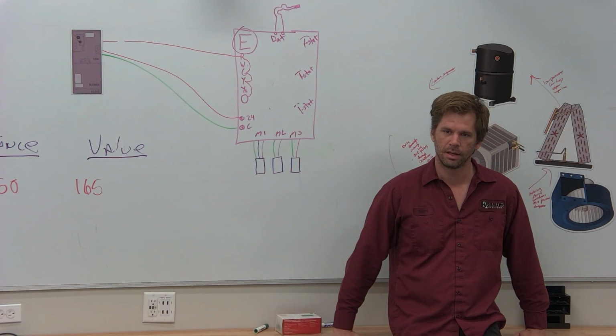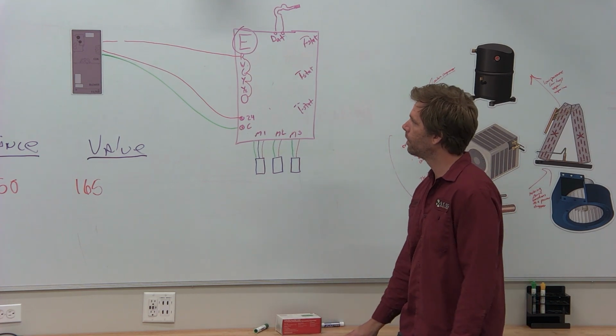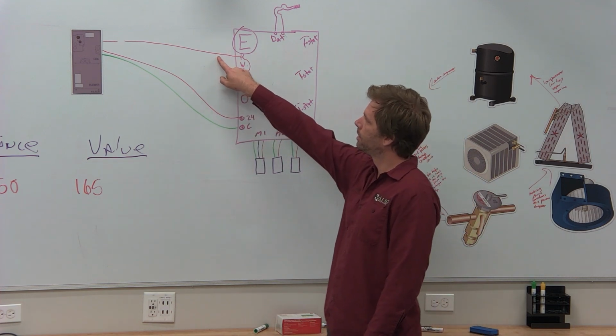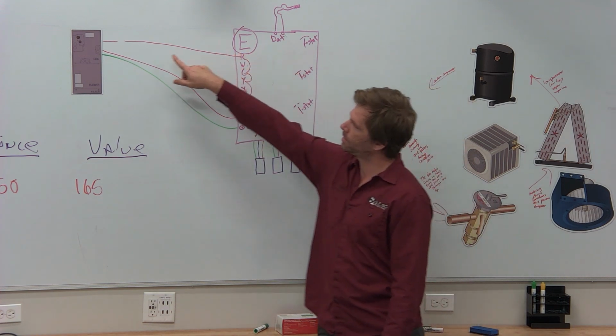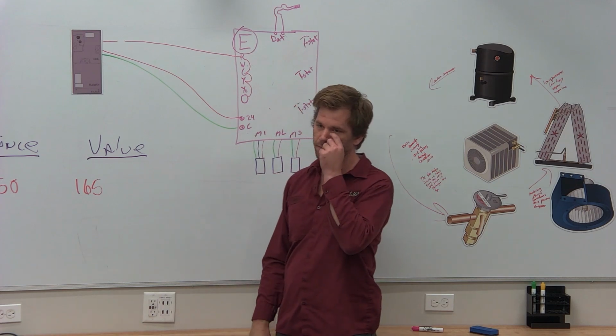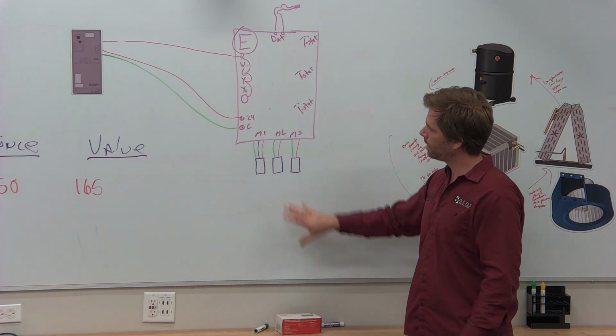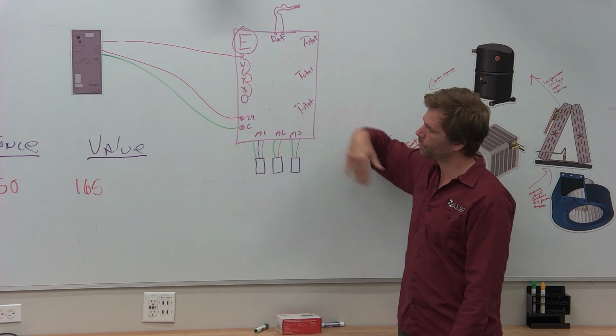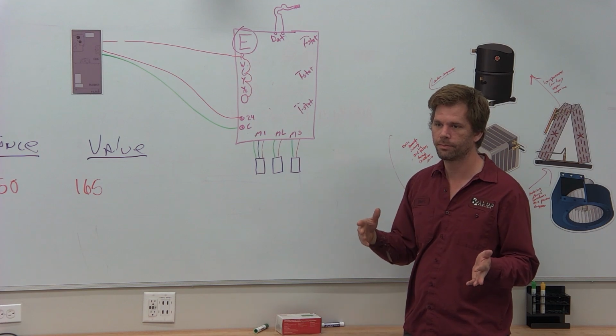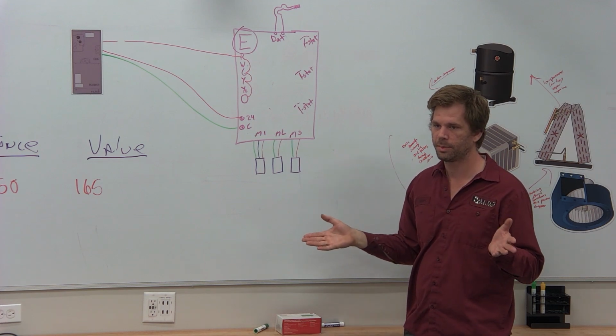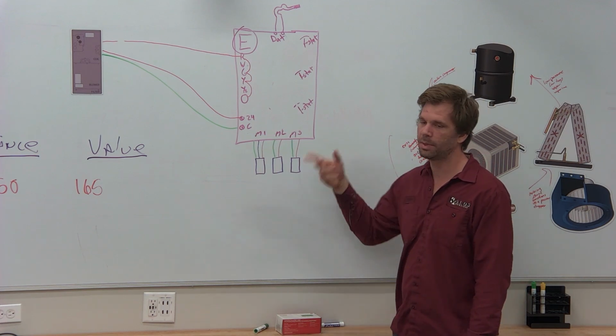The thermostat has a display, it says it's calling, so you're not thinking float switch, because we don't usually walk in and have a blank thermostat when it's not its own system. And so when you actually have red killed powering to the equipment, so some safety is keeping red off, everything here is going to be functioning normally. Your motors will open and close. Your thermostats will have a display, they'll be calling, but your equipment's just not turning on.